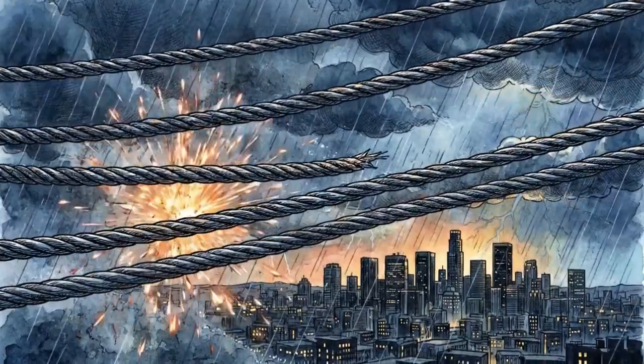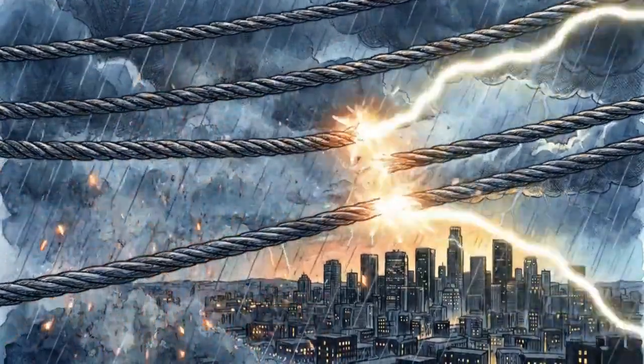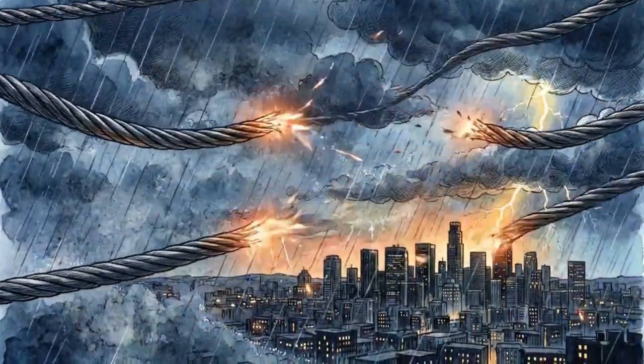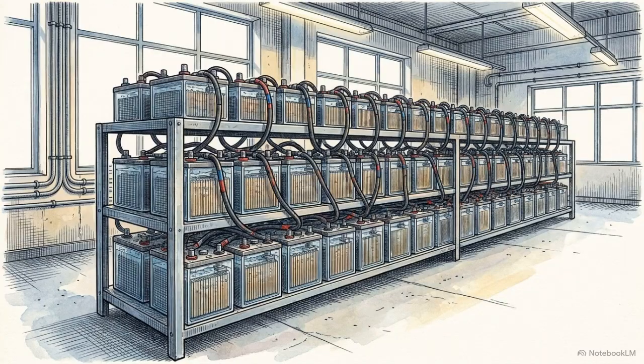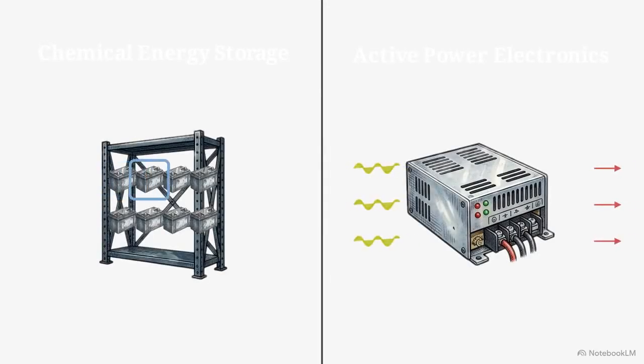When the AC grid goes down, the equipment designed to protect and restore it requires power to operate. That power comes from the substation's DC battery system. It's the absolute last line of defense, standing between a temporary fault and a catastrophic blackout. Bringing one of these systems online necessitates a multi-phase validation of both chemical energy storage and active power electronics.